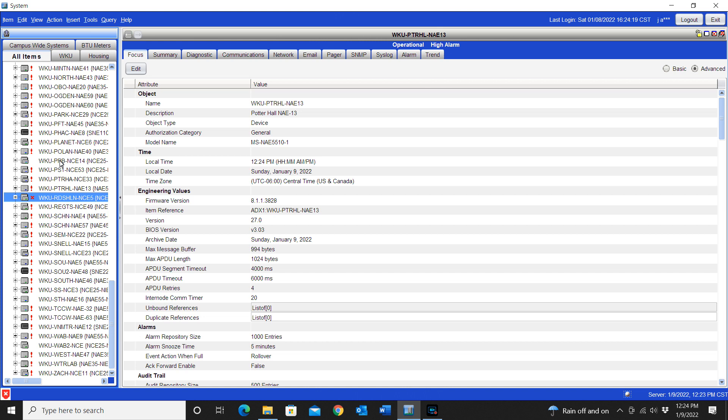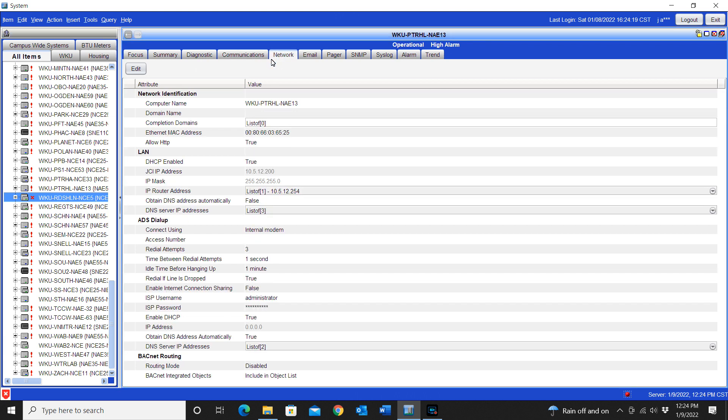But since then, as I mentioned earlier, when IT changes an IP address for a device, that file is not being updated automatically, either being network security or whatever it is. It is an issue that does happen occasionally. So going in, correcting the IP address, making sure that it matches with the IP address on your device can typically resolve the problem, or at least that it has in our case.